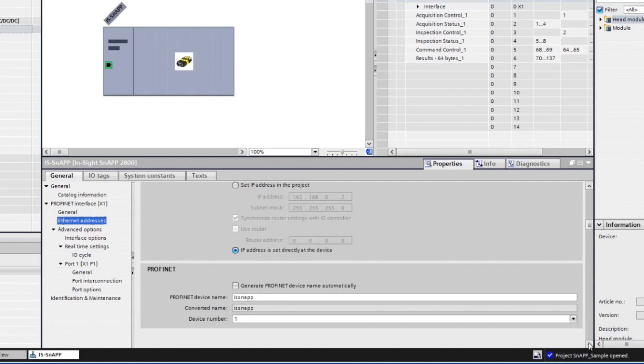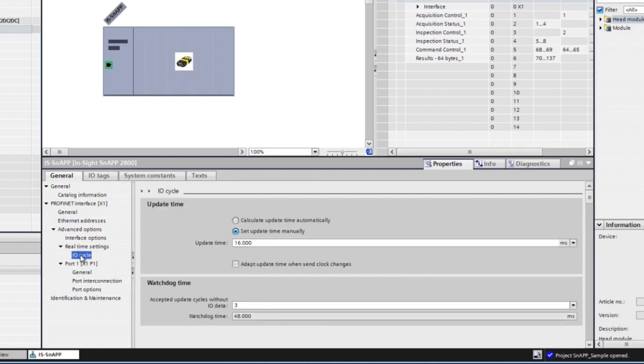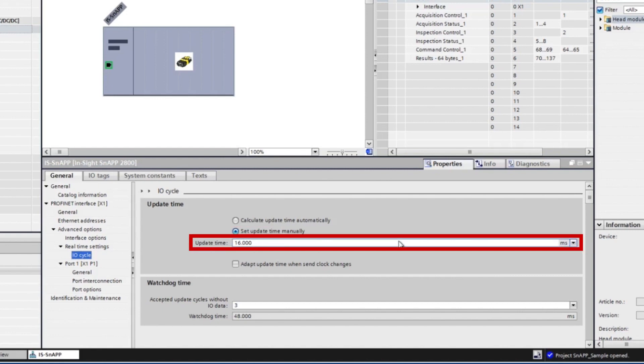You also have the option to specify IO cycle time. Select the Set Update Time Manually option and set the Update Time option to 16ms to account for the speed needed for updates to occur between the In-Sight SnAPP sensor and PLC.